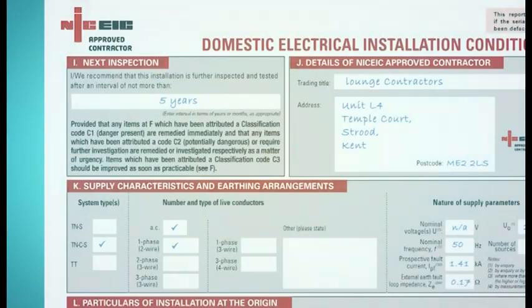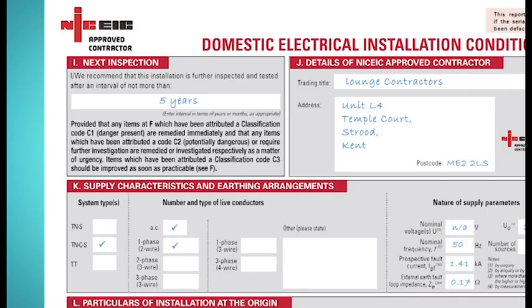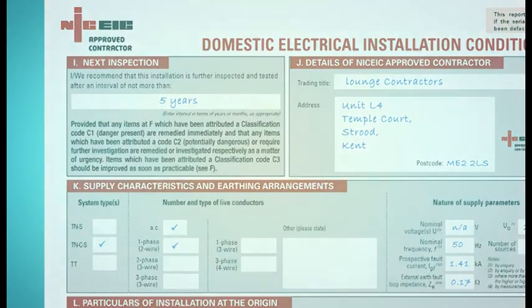And are you going to put a date if there are C1s or C2s? Oh yes, Dave. Let me read you exactly what it says in this section. Provided that any item at F, which has been attributed a classification code C1, which is danger present, are remedied immediately, and any items which have been attributed a code C2, potentially dangerous, or require further investigation are remedied or investigated respectively as a matter of urgency. Items which have been attributed a classification code C3 should be improved as soon as practicable. So that paragraph makes it very clear that this is a report from us, the contractor, to the homeowner, but the responsibility for remedial work clearly lies with the homeowner.